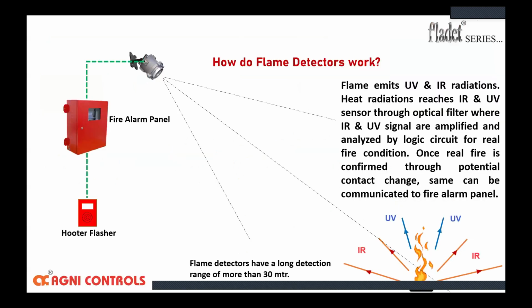So as explained previously, this is a small animation where a flaming fire has occurred. And as you can see, the fire emits IR radiations coming off from the bottom and UV radiations coming off from the top of the flame. Once it is detected, the detector has operated here. It gives a signal to the main fire alarm control panel, which in turn gives output to the strobe horns or your fire suppression systems or any logics as per the designed logics.